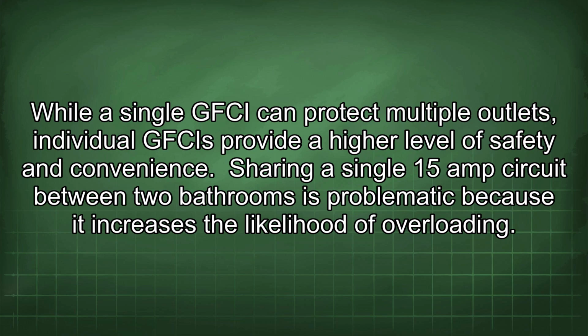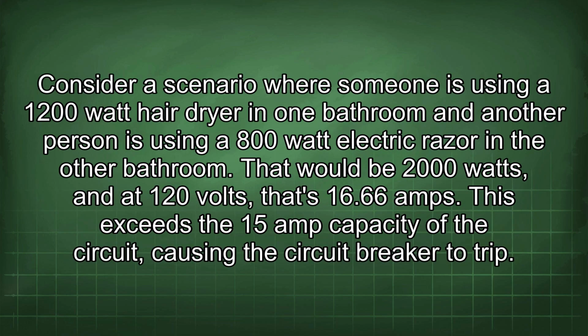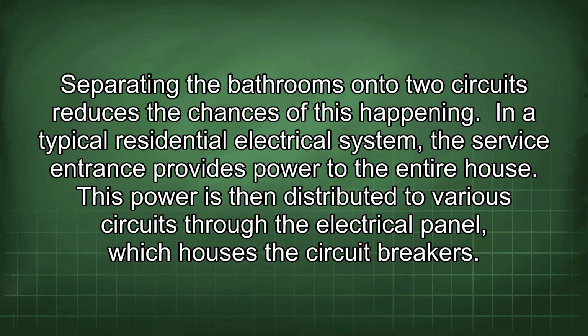Sharing a single 15 amp circuit between two bathrooms is problematic because it increases the likelihood of overloading. Consider a scenario where someone is using a 1200 watt hairdryer in one bathroom and another person is using an 800 watt electric razor in the other bathroom. That would be 2000 watts, and at 120 volts, that's 16.66 amps. This exceeds the 15 amp capacity of the circuit, causing the circuit breaker to trip. Separating the bathrooms onto two circuits reduces the chances of this happening.